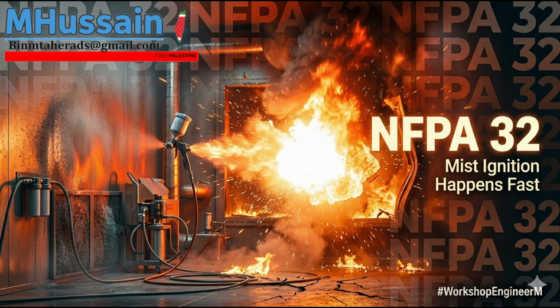But the TIAs are where the real risk management lies. Absolutely. Tentative interim amendments are changes issued between the regular revision cycles. Because things move too fast for a 5-year cycle. Exactly. They are triggered because a new urgent hazard has been identified or maybe a critical new technology has emerged that the current edition just doesn't cover safely. So checking the codes and standards section on the NFPA website isn't just some administrative chore. It is mandatory risk management. It really is. You have to know if a TIA was issued, like yesterday, that completely alters the required safety interlocks for a specific solvent class you're specifying today.